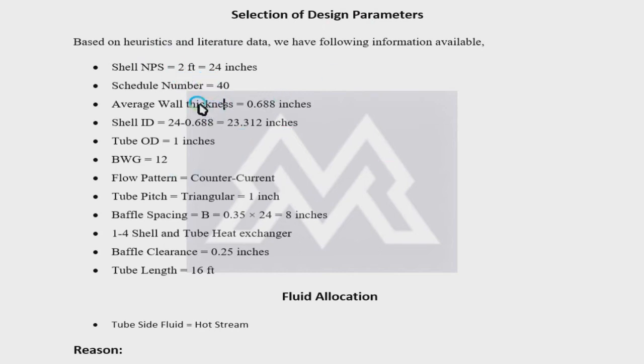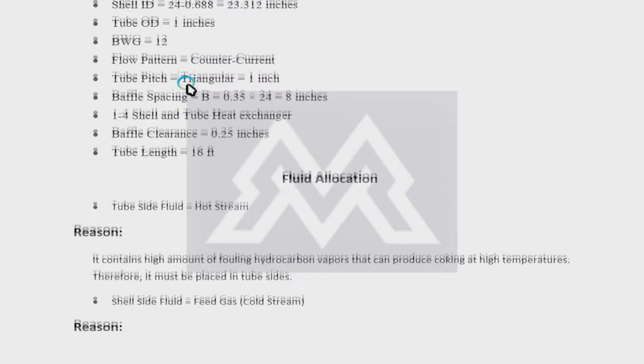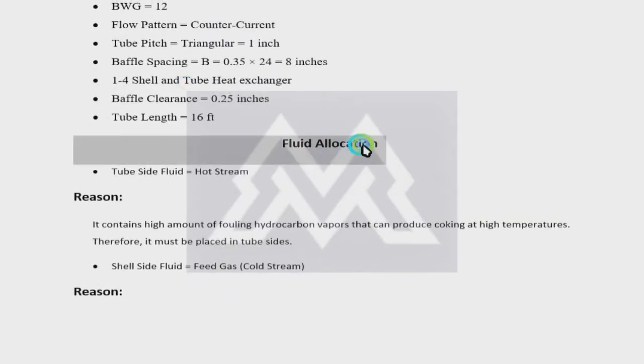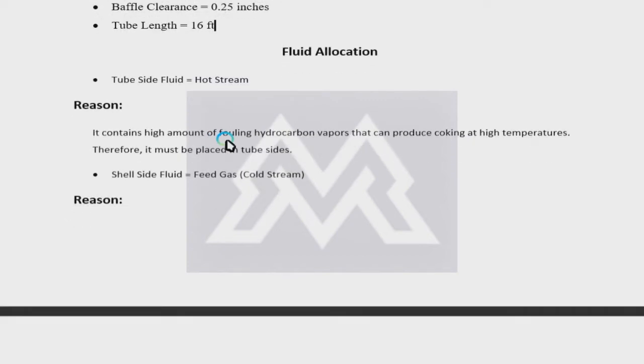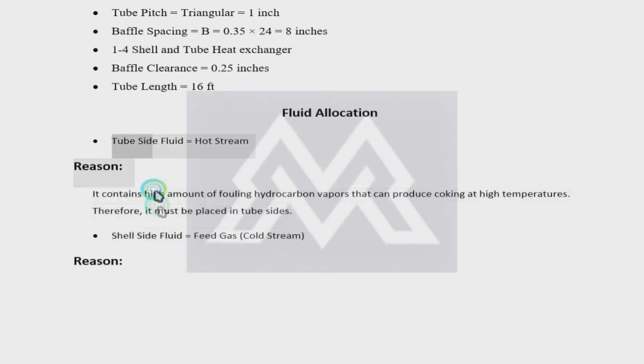For example, here we have vapor flows, and vapor takes a large area, so I have selected the largest standard shell NPS available. A 1-inch tube size is very optimum because tubes can be arranged in large numbers to increase contact area. The next step is fluid allocation. Fluid allocation is based on heuristics: high fouling, corrosive, or high-temperature fluids must be placed in the tubes. Larger flow rates should be placed in the larger area — the shell is larger in most cases — so you must reason properly about where to place each fluid.